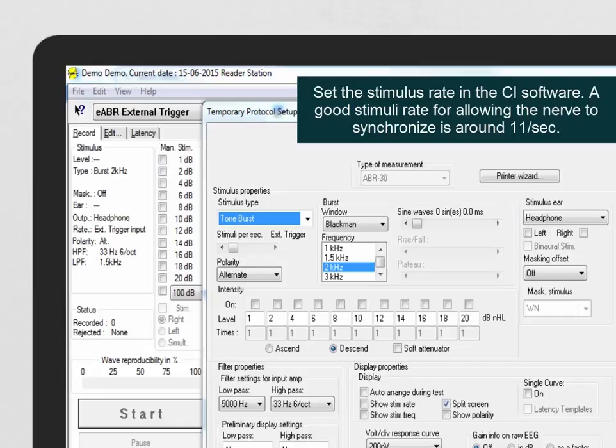The Eclipse is able to record a measurement every time a 5-volt source trigger signal with a duration of greater than 10 milliseconds is sent from the cochlear implant stimulator. The stimulus rate from the cochlear implant stimulator must not exceed 50 per second in order to allow sufficient recording and processing time. A good stimuli rate for allowing the nerve to synchronize is around 11 per second.